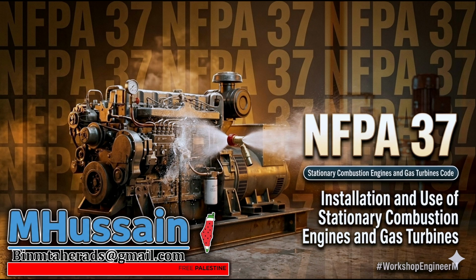Yeah, but a 15 kilowatt or say a 30 kilowatt standby generator sitting behind a small office building or a convenience store, that triggers the full weight of the standard. So suddenly you're bound by all these crazy clearance and ventilation rules just for keeping the office fridges running. Exactly. The moment it's hardwired into a permanent structure, you are in NFPA 37 territory.